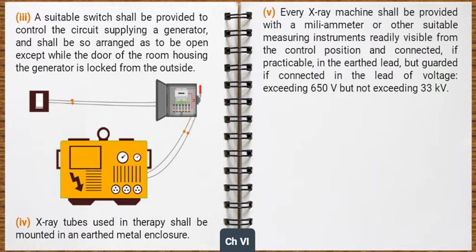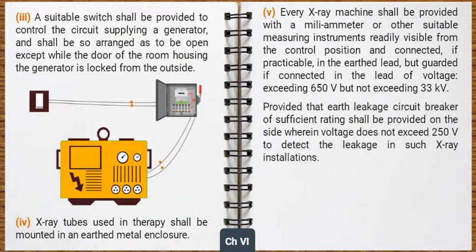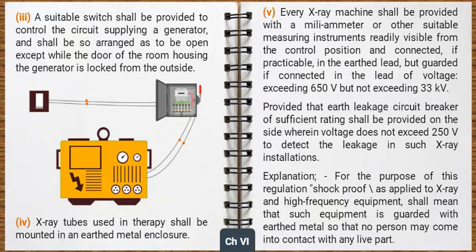Every X-ray machine shall be provided with a milliammeter or other suitable measuring instruments readily visible from the control position and connected, if practicable, in the earthed lead but guarded if connected in the lead of voltage exceeding 650 volt but not exceeding 33 kilovolt. Provided that an earth leakage circuit breaker of sufficient rating shall be provided on the side wherein voltage does not exceed 250 volt to detect the leakage in such X-ray installations. Explanation: for the purpose of this regulation, shock-proof as applied to X-ray and high-frequency equipment shall mean that such equipment is guarded with earthed metal so that no person may come into contact with any live part.